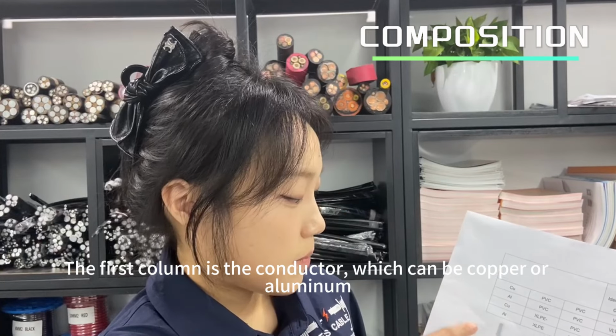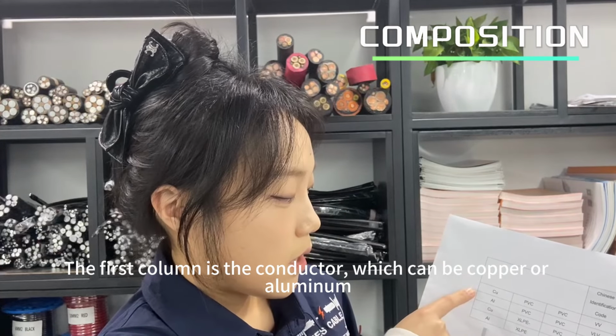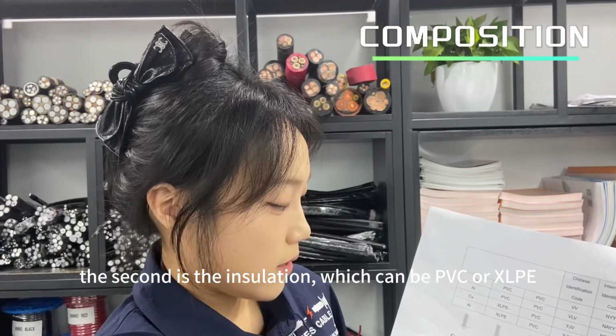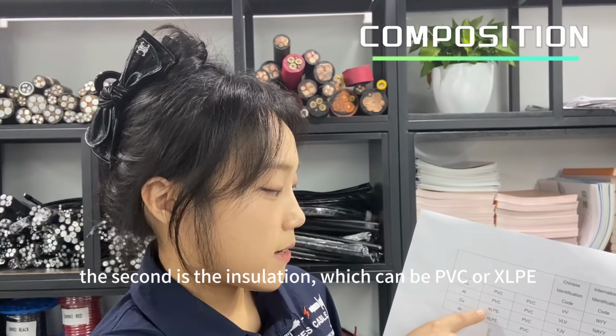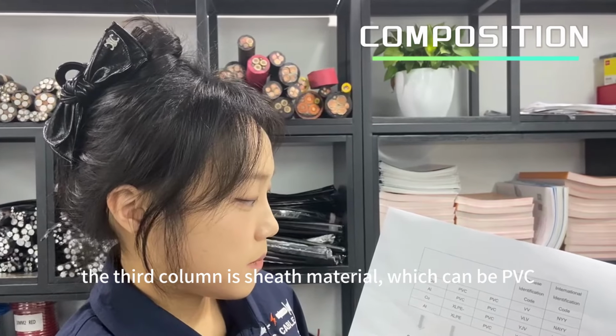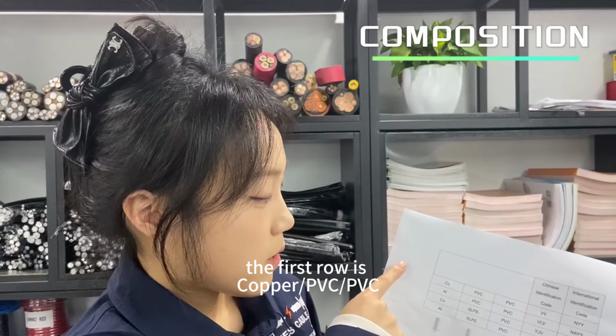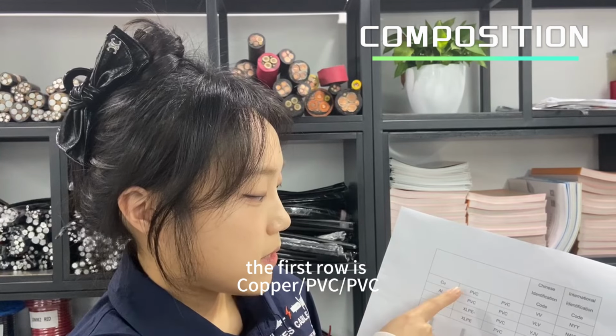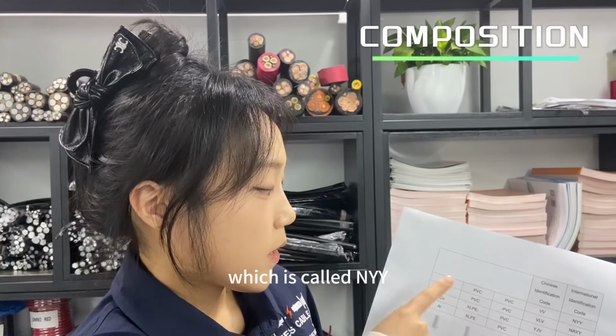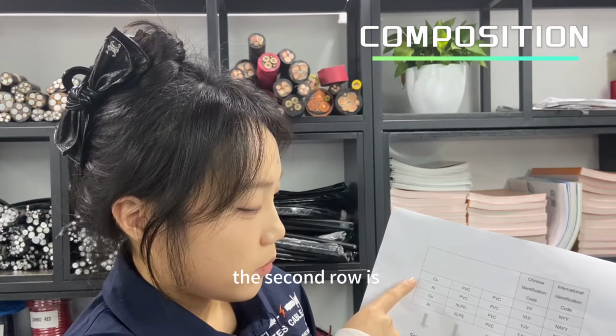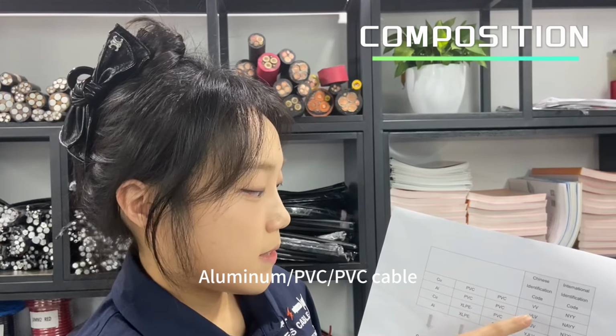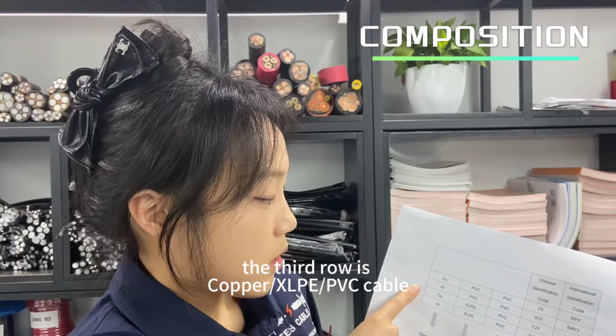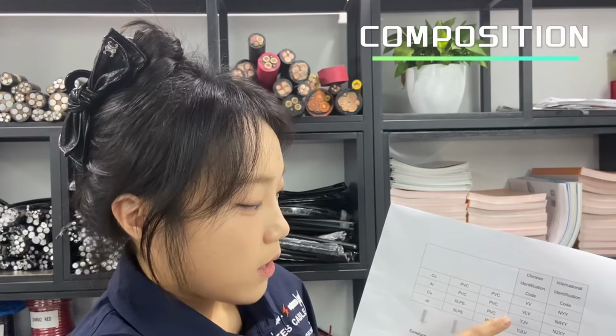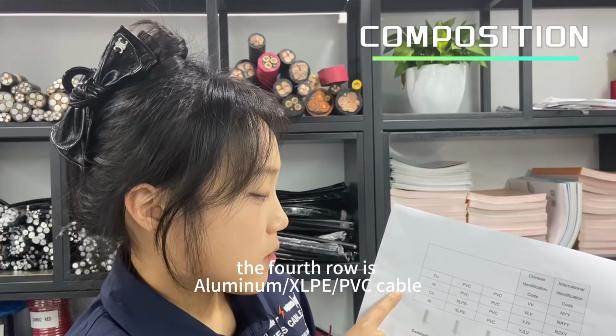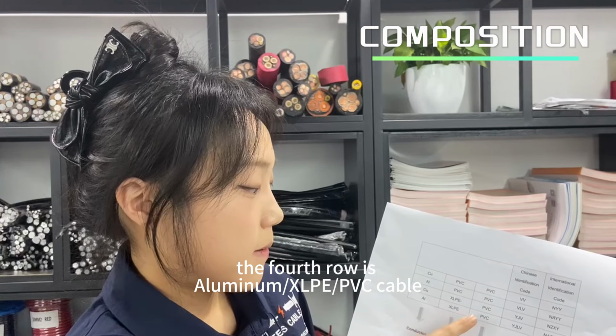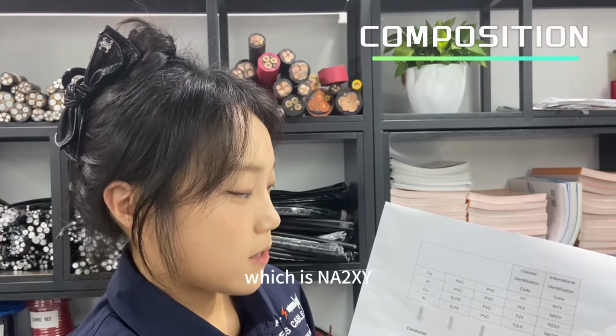The first column, conductor, copper or aluminum. The second is insulation, PVC or XLPE. The third column, sheath, PVC. The first row, copper, PVC, PVC, cable is NYY. The second row, aluminum, PVC, PVC, cable is NAYY. The third row, copper, XLPE, PVC, N2XY. The fourth row, aluminum, XLPE, PVC, cable is NA2XY.